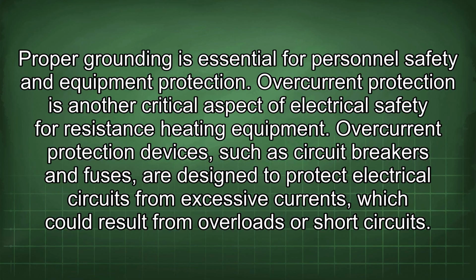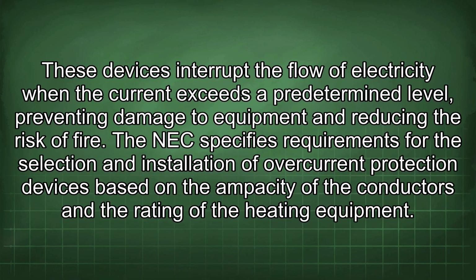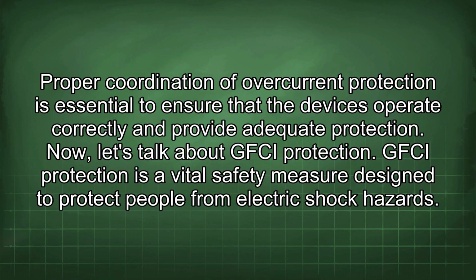Overcurrent protection is another critical aspect of electrical safety for resistance heating equipment. Overcurrent protection devices, such as circuit breakers and fuses, are designed to protect electrical circuits from excessive currents, which could result from overload or short circuits. These devices interrupt the flow of electricity when the current exceeds a predetermined level, preventing damage to equipment and reducing the risk of fire. The NEC specifies requirements for the selection and installation of overcurrent protection devices based on the ampacity of the conductors and the rating of the heating equipment. Proper coordination of overcurrent protection is essential to ensure that the devices operate correctly and provide adequate protection.